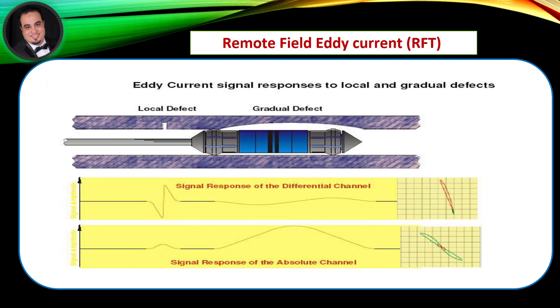Remote Field Testing (RFT) is commonly used for inspection of ferrous carbon steel tubes. RFT has equal sensitivity to inside diameter and outside diameter indications and can detect and size corrosion and pitting, as well as baffle cuts.